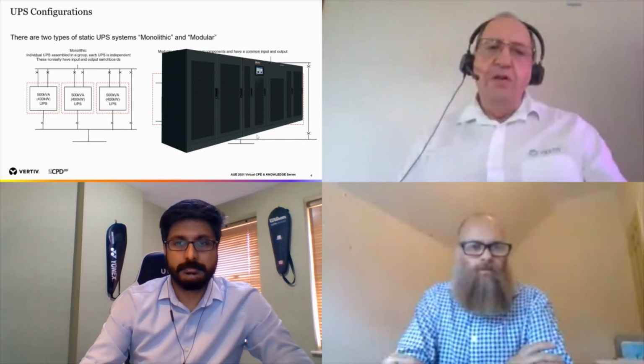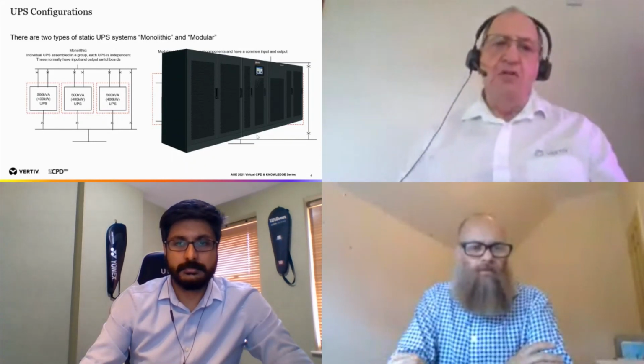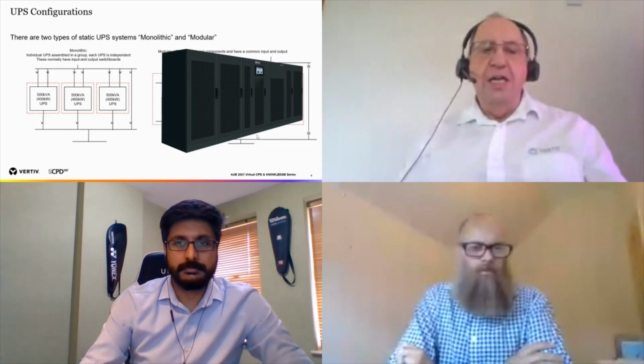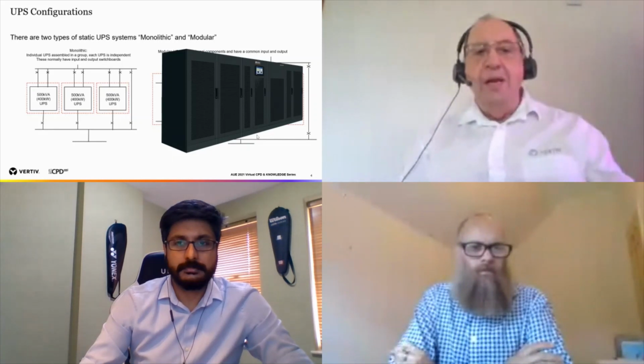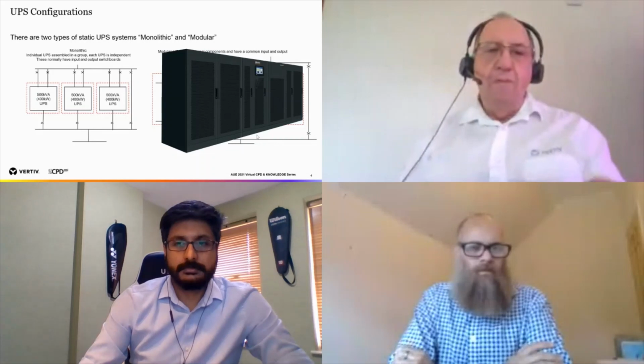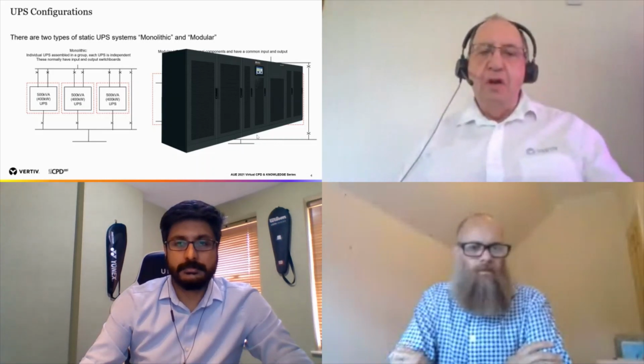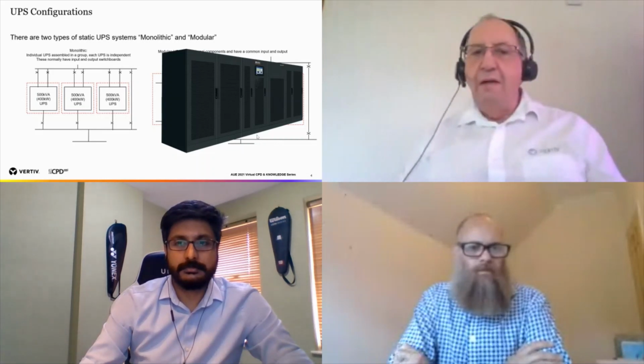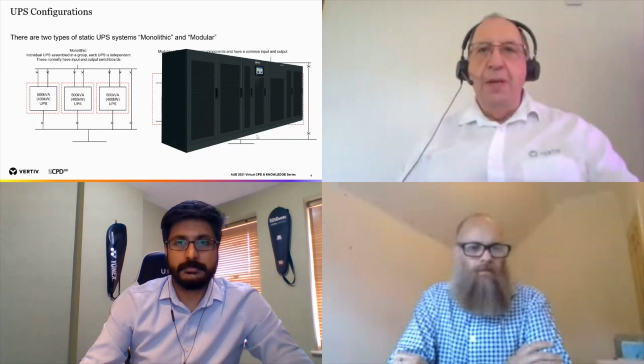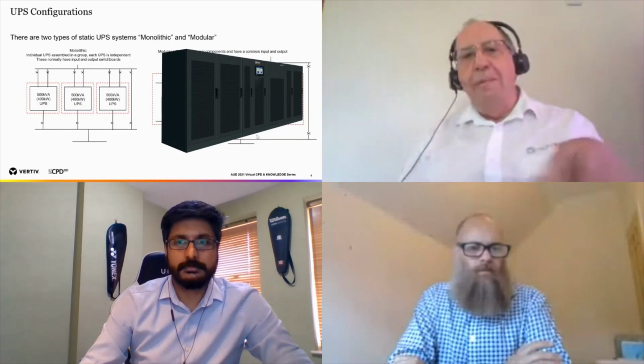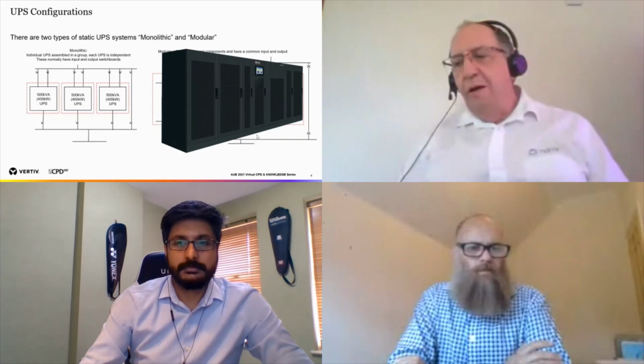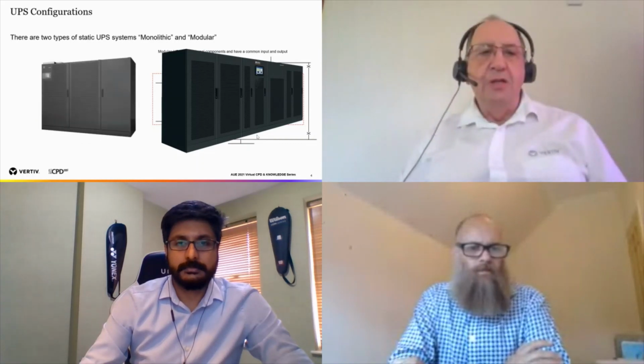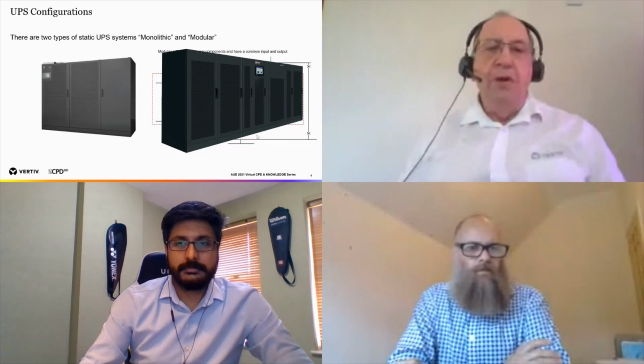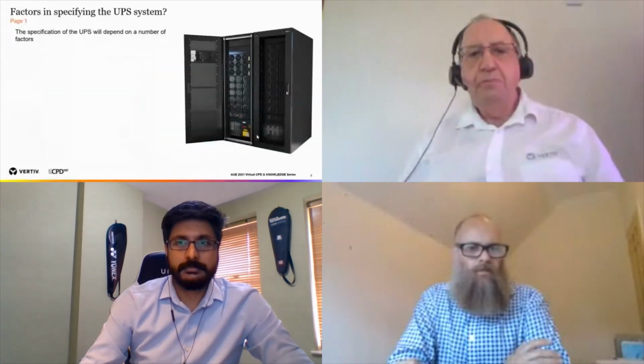But on the traditional side, the monolithic side, it is possible to have independent UPSs side by side, arranged so that one UPS could be taken out for a service, another UPS could fail, and all of the load would go on to the third UPS. So resilience is a big part of specifying and planning applications. And there's a traditional monolithic UPS.